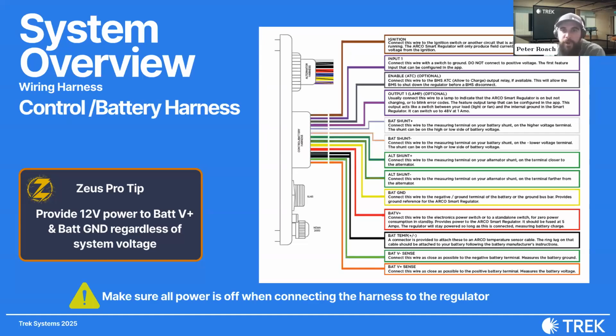And then the battery ground - this connects to the negative or ground terminal on the ground bus bar, as well as this BAT-V plus, which connects at the Lynx distributor typically. A Zeus pro tip here: if we're working with a 24 volt or 48 volt system and charging with a Zeus, providing 12 volt power to the BAT-V plus and battery ground, regardless of the voltage we're charging with, is very ideal. We've seen a few situations where that has smoothed out some rough communication, because the Zeus likes to operate on that 12 volt.